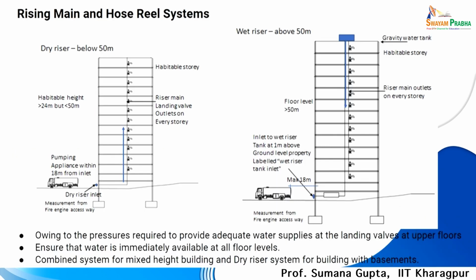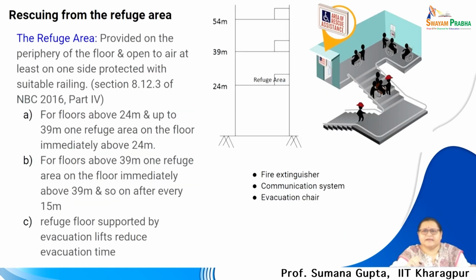These are the common slides which we discussed, the dry riser, the wet riser. Above 50 meters it is always the wet riser, below 50 meters it is the dry riser, which are mandated in our codes and standards, to be built within the system. Refuge areas, this has also been discussed, they should come first at 24 meter height, then after another 15 meters, another 15 meters you should get.